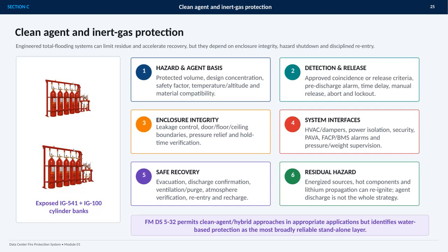This section focuses on clean agent and inert gas protection for data centers. Engineered total flooding systems can minimize residue and speed recovery, but they only work as intended when the room, controls, and recovery process are managed as one system. The key point is that agent discharge is not the whole fire protection strategy.